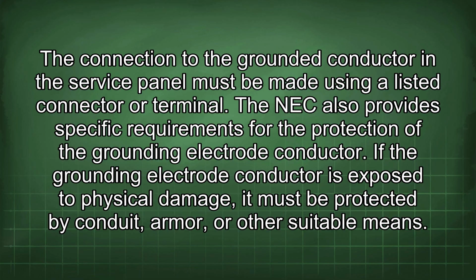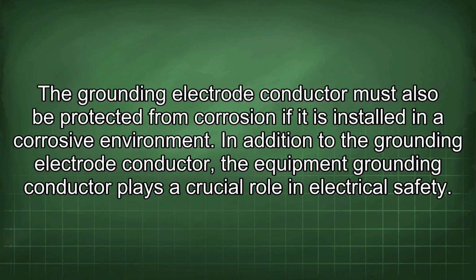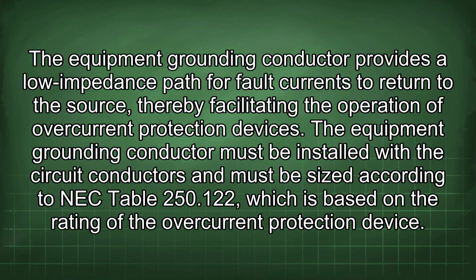The NEC also provides specific requirements for the protection of the grounding electrode conductor. If the grounding electrode conductor is exposed to physical damage, it must be protected by conduit, armor, or other suitable means. The grounding electrode conductor must also be protected from corrosion if it is installed in a corrosive environment. In addition to the grounding electrode conductor, the equipment grounding conductor plays a crucial role in electrical safety. The equipment grounding conductor provides a low impedance path for fault currents to return to the source, thereby facilitating the operation of overcurrent protection devices.